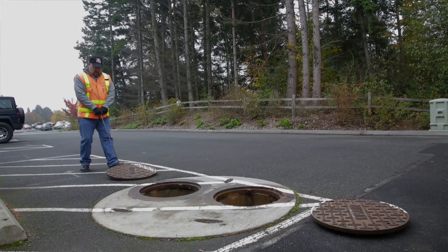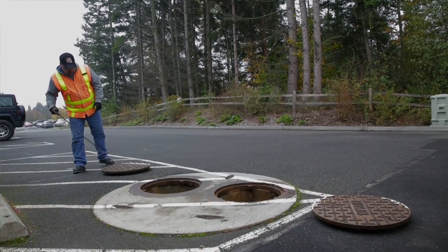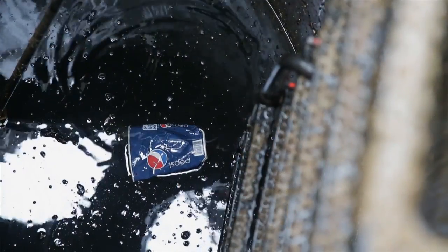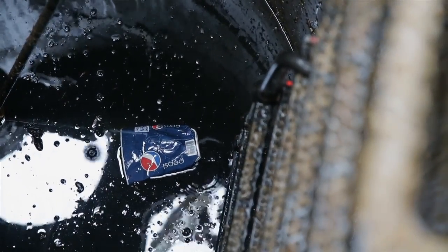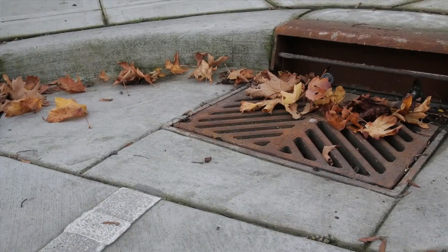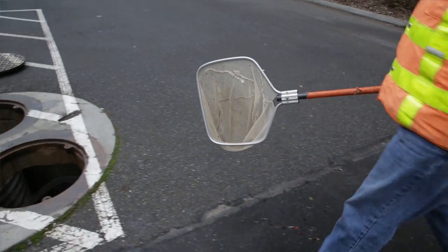Just after you pop the lids, one of the things you're commonly going to see is what we call floatables. That's the floatable debris, paper plates, plastic bags, Coke bottles that will be floating on the top of the water. Now, one of the things that I always like to mention is that vegetation, sticks, leaf debris, even though it's organic, it's still debris. It can cause a control structure problems. So that material needs to be removed also.